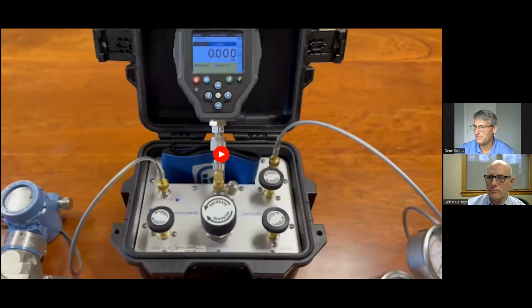I'm going to double down on the quick test hoses, the connections. We've got a 45 on the gauge there and another QD. And then on the regulator, we had the X-Reg, which has a quick connect to the nitrogen bottle. All the Ralston stuff's there, allowing for easy connection, easy hookup, and quick, precise testing with nitrogen just by controlling the volume.